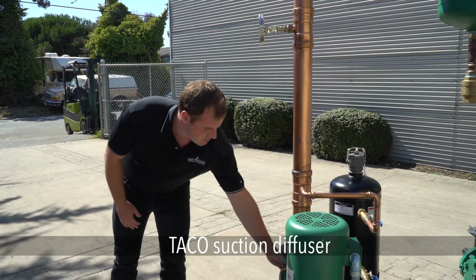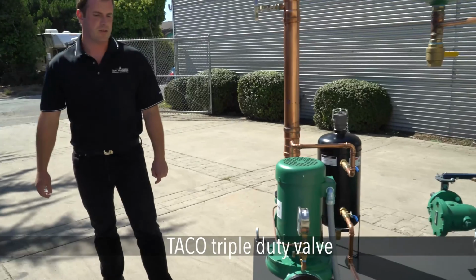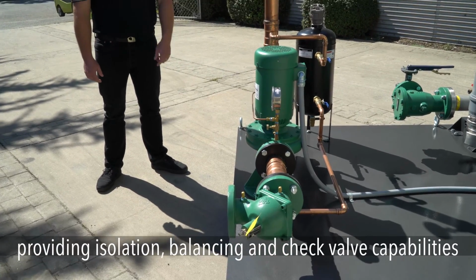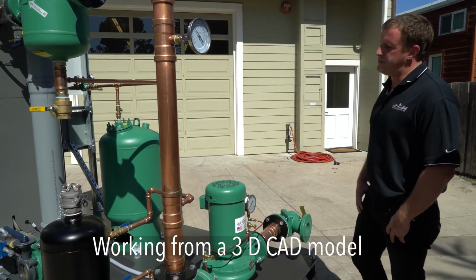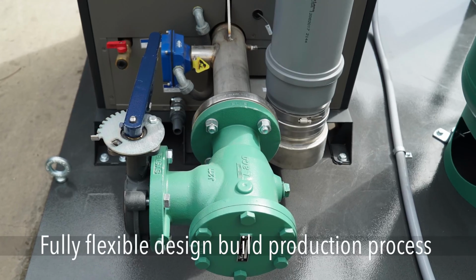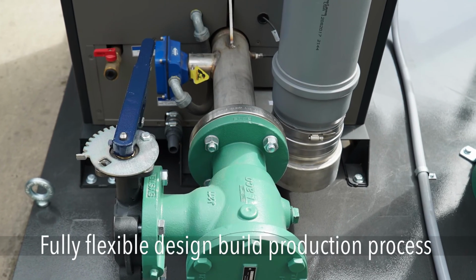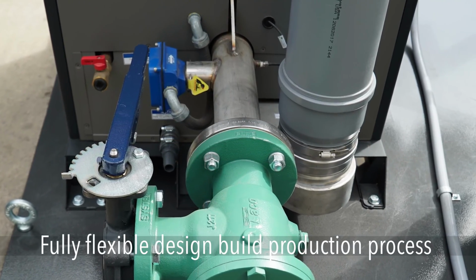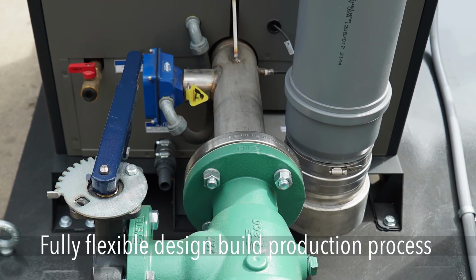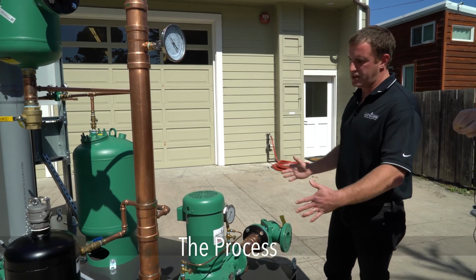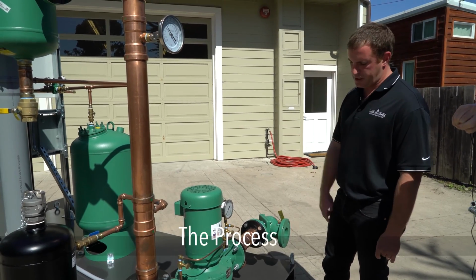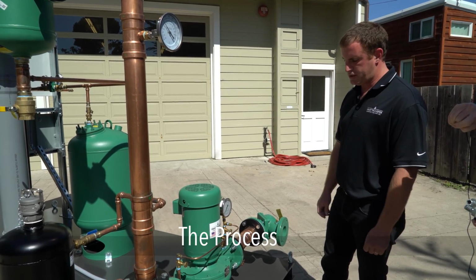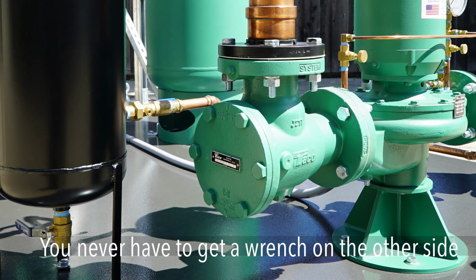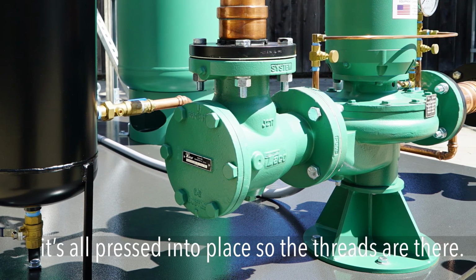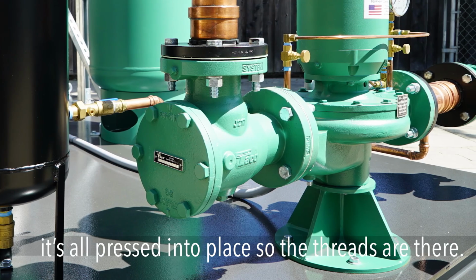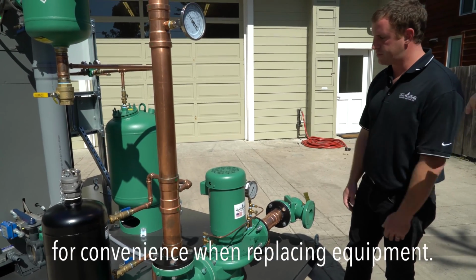We have a Taco suction diffuser as well as a Taco triple duty valve providing isolation, balancing, and check valve capabilities. We work off of a 3D CAD model. There's always design-build factor within our production. If something makes more sense or it'd be more efficient to move placement of any of the components, we have full flexibility. We get the skid platform powder coated. We lay everything out one component at a time, counterbore each hole, and then press the rivet nut into each hole. Basically, you never have to get a wrench on the other side to remove any of the equipment. It's all pressed into place so the threads are there, and you just unbolt it if you ever need to replace a piece of equipment. It'll all just pop right off.